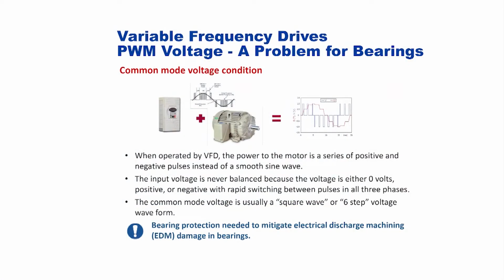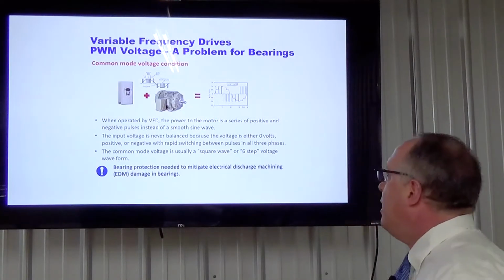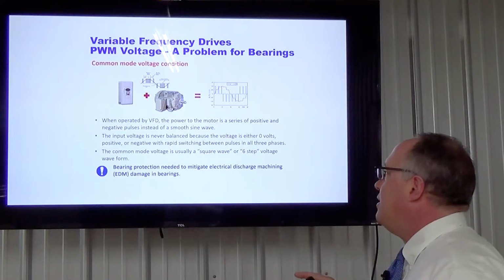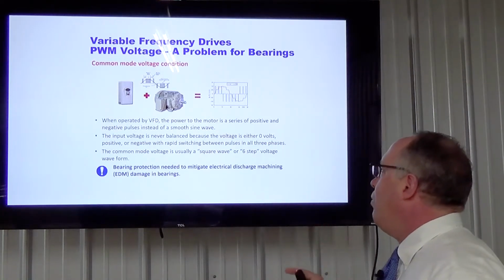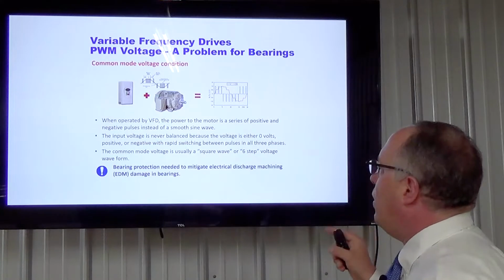But let's put a variable frequency drive on this. Our pulse width modulated voltage can be a problem for the bearings, and that's caused in the common mode voltage condition. When operated by a VFD, the power to the motor is a series of positive and negative pulses that are sent. The input voltage is never balanced because the voltage is either 0 volts, positive or negative, with rapid switching between pulses in all 3 phases. Common mode voltage is usually a square wave or a 6-step voltage waveform.